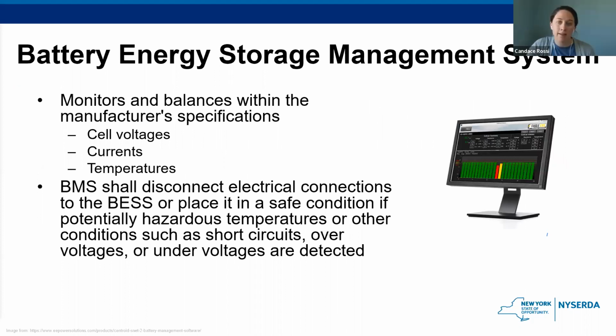So once again, we have the battery management system. So this is considered an instrumental safety feature of the system and should be considered the eyes and ears of the battery system's health. This device is constantly monitoring the state of health of the system, and if the battery management system were to fail, the system would lose a major safety feature. This is probably the most important feature of the system in its effort to prevent the thermal runaway event, as it's able to detect anything that is abnormal and hopefully able to isolate it timely.